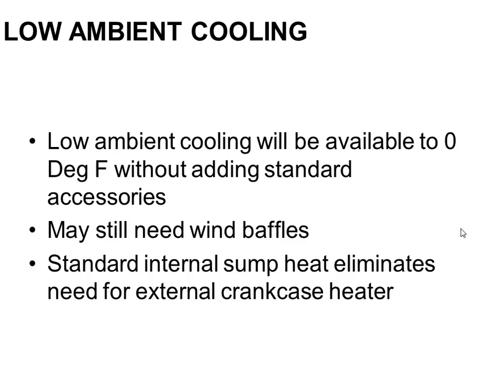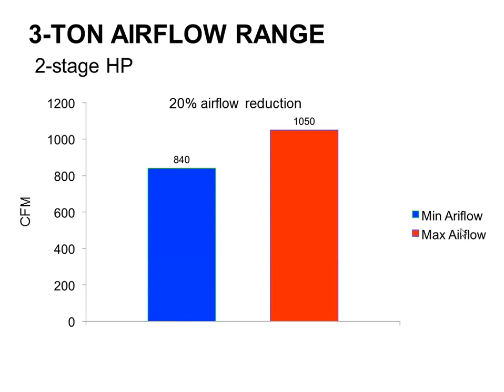You can do low ambient control with these guys, down to 0 degrees without adding anything additional. Because the condenser fan is already variable speed, we don't have to add anything special there. The Infinity and Evolution controls can already ramp him down for low ambient usage. And there's also an internal sump heater, so I don't need to add a crankcase heater on there. You probably still need to add wind baffles if you're going to put this on a roof or something like that where you're going to have direct prevailing wind.